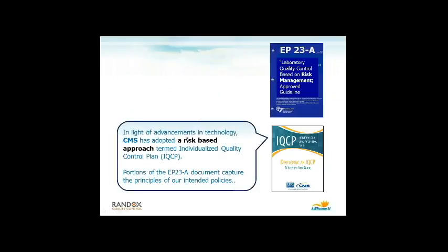There are two documents people are talking about. One is IQCP, a step-by-step guide developed by CMS in the United States, and the other is EP-23A, a laboratory quality control based on risk management. This is a regulation for people in the United States. In light of advances in technology, CMS has adopted a risk-based approach that they call individualized quality control plan.